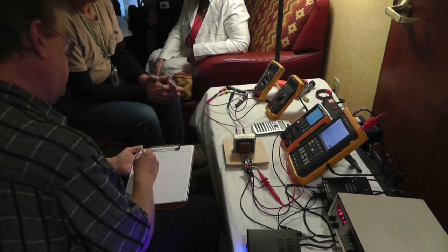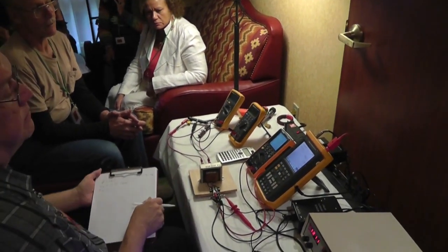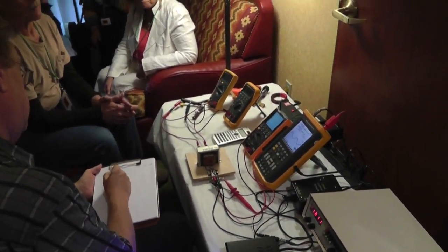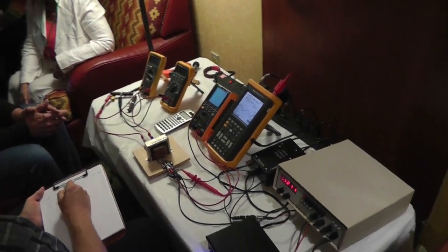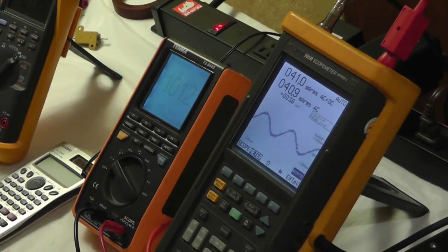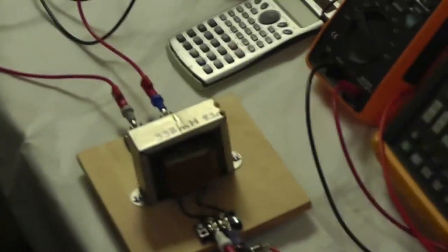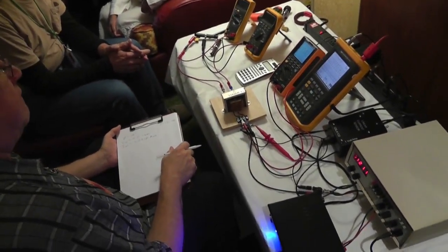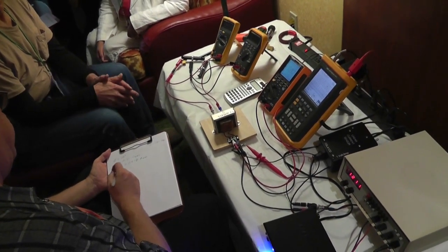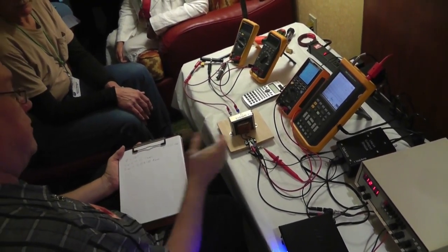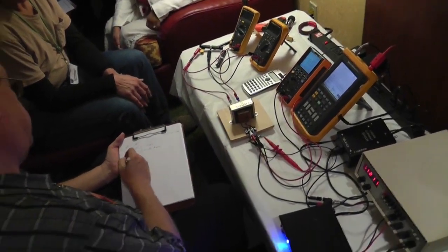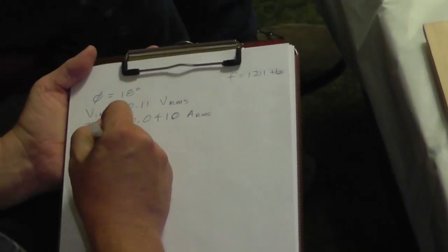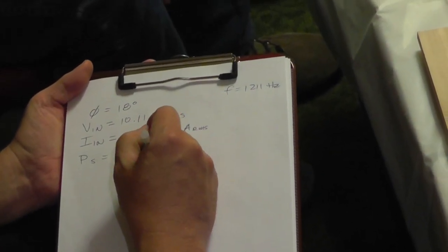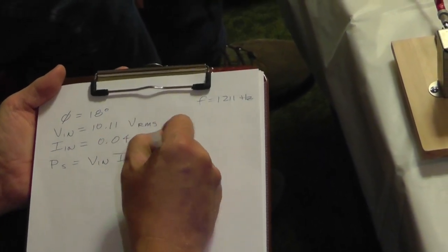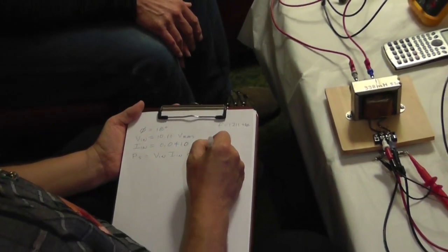The current input we pick up from this sensor, and that's reading 41 milliamps RMS. And then, of course, we have that phase angle of 18 degrees. So we can do a power calculation. We see how much power is coming into that transformer by doing voltage times the current times the cosine of 18 degrees.